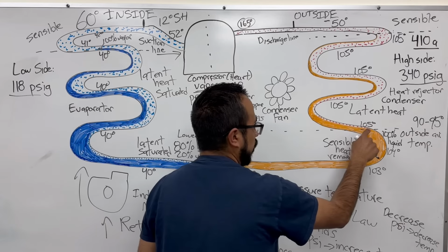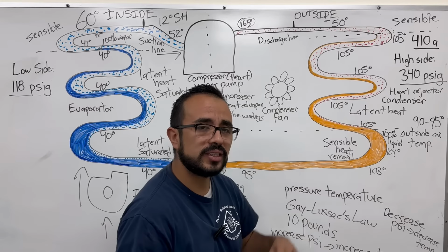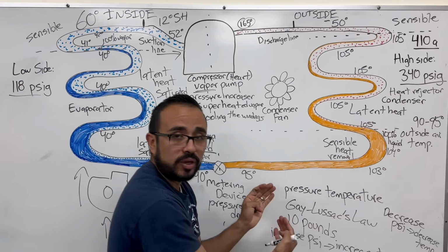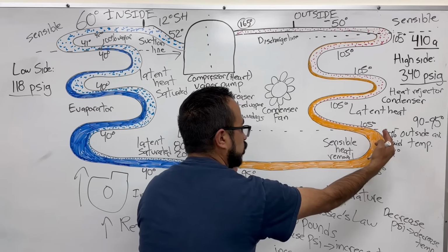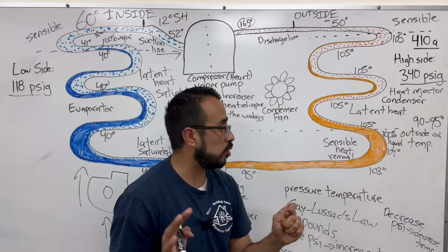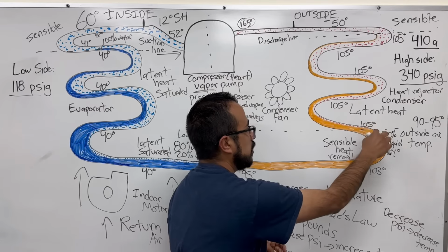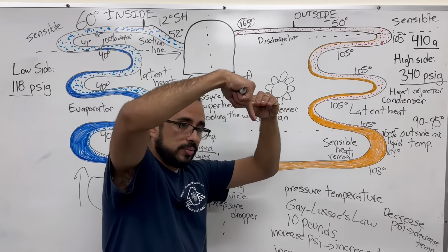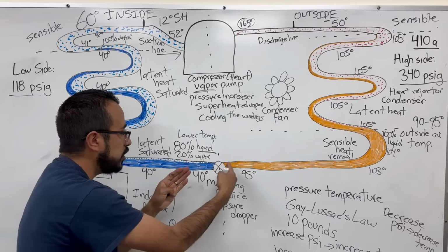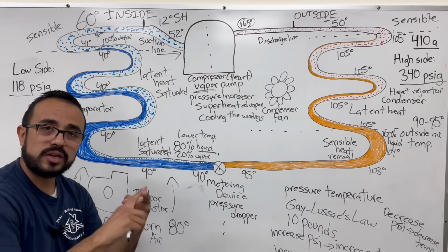And so once the last molecule of vapor is gone, we then have 100% liquid. That is when we can actually start to remove sensible heat. And so we want a good measure of subcooled liquid here, right? We want liquid because that tells us you've got 10 degrees of subcool. If you have 10 degrees of subcool, not only did you change state, but you turned to a liquid and you still dropped 10 degrees. So then we can now meter that, because we can meter or drop the pressure. If it's vapor, boom, saturated. If you know saturated, you know your temperature.